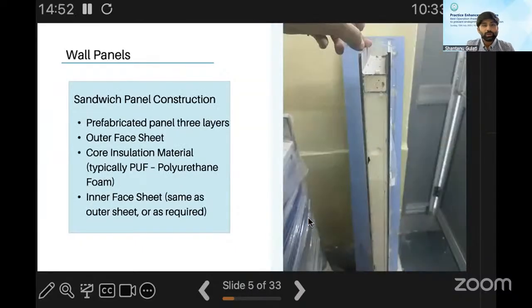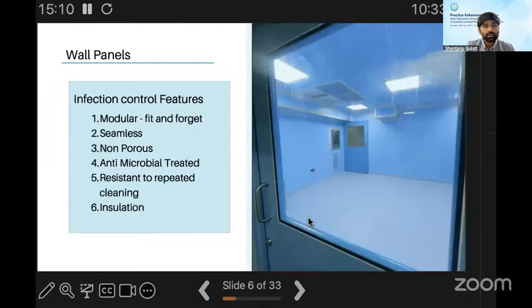What is important here is that most of these are available as sandwich panels. What that means is between 2 surfaces of the same panel, they put a certain density of PUF or polyurethane foam, which provides the thermal and the sound insulation that is required. With respect to the infection control features, these panels are modular, so they can be fit quite fast as compared to a brick system. They are seamless, non-porous, treated and certified for antimicrobial activity, resistant to repeated cleaning, and they provide thermal and sound insulation.